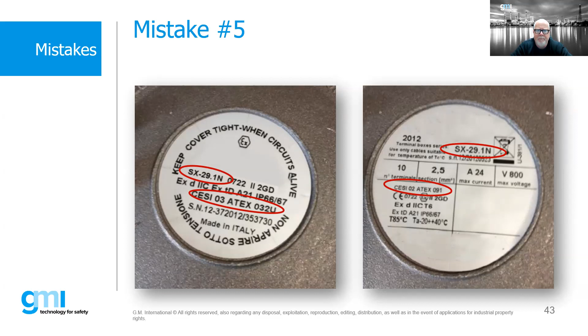Mistake number 6 is conditions for safe use on EX equipment. Any piece of EX equipment that has an X condition means there is some sort of condition for this particular piece of equipment to be safely used. This is also a mistake because some people buy it, it's certified, assembly certified, but they pay no attention to the X condition. We have to read the information in the X condition in the certificate, which tells us how to safely use this equipment. Be aware of that. Any product with an X condition will have specific conditions for use, so make sure we're following them.